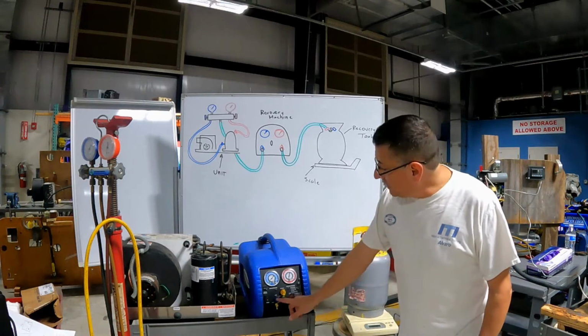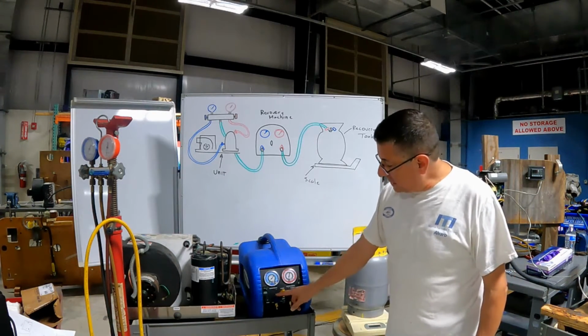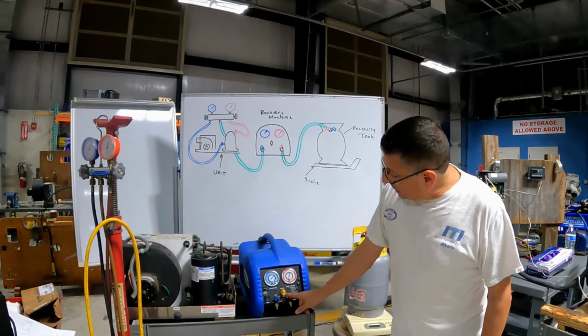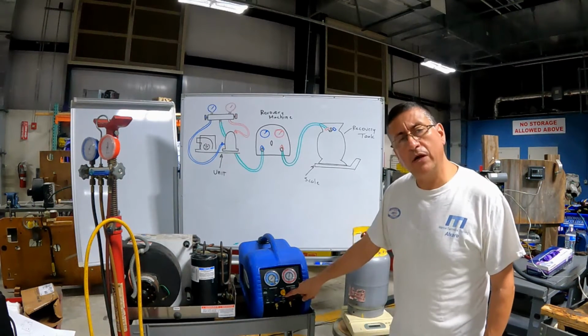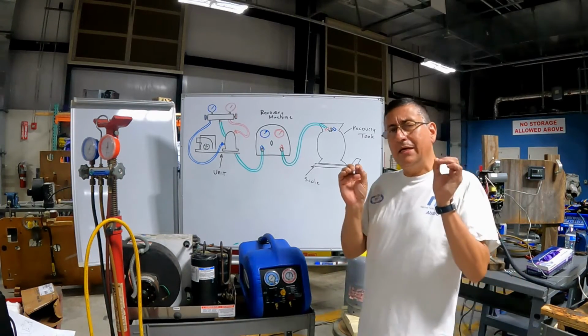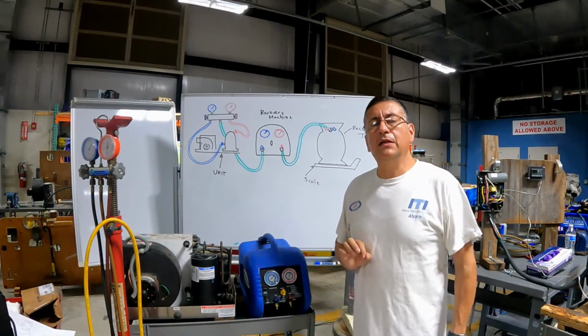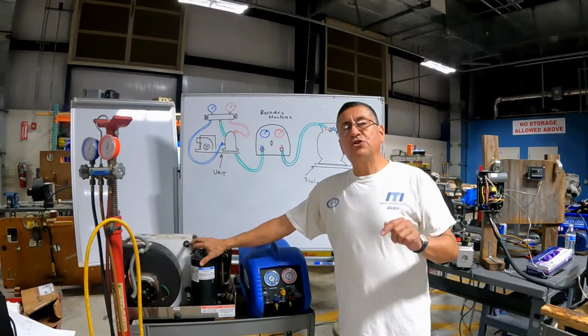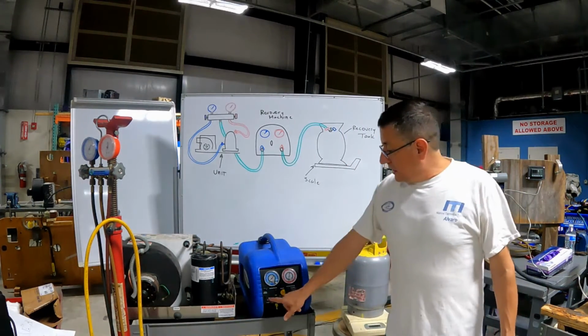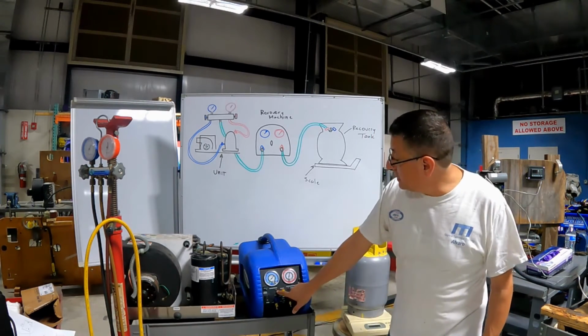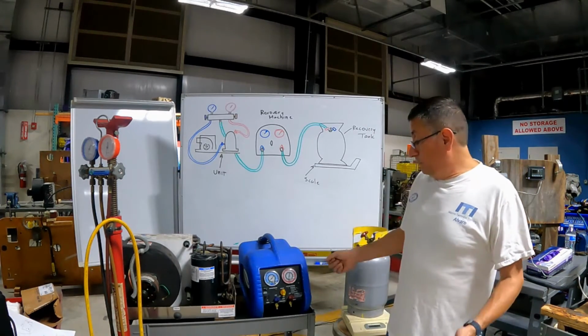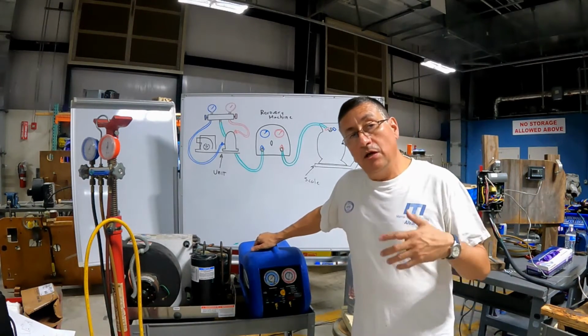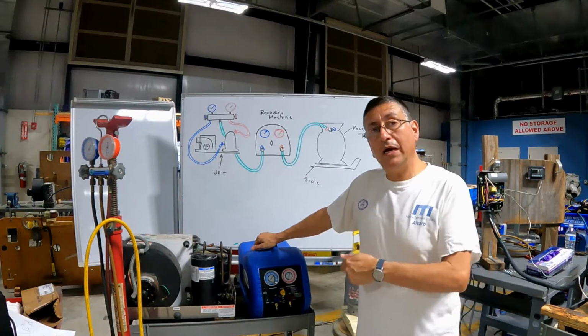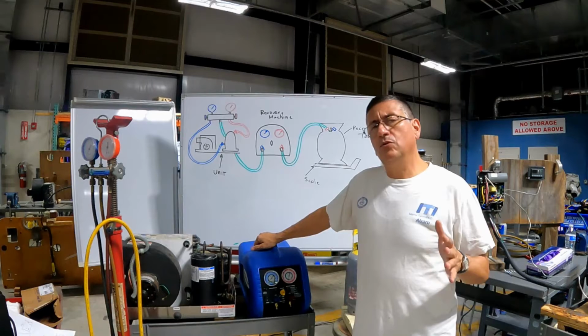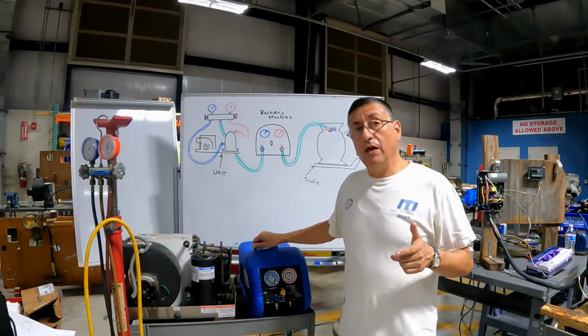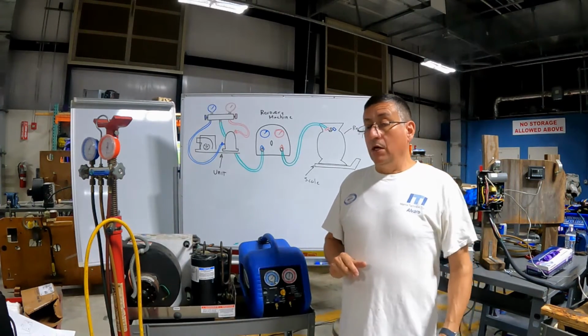Remember that this equipment has two valves, one valve for the low pressure side and the gauge for the low pressure side, another valve for the high pressure side, and the middle one in order to select recover or purge. We are going to purge the system at the end of the process in order to eliminate small amounts of refrigerant inside of the unit. We are going to purge the system at the end of each method. All right, and the on-off switch, and the LED to indicate that the process is complete. It's simple. This is a great piece of equipment. If you will be dedicated to working on air conditioning equipment, I recommend you try to buy one of those units. There are different manufacturers. Try to check the reviews of the equipment on the internet in order to buy the best equipment possible. Ready? We are ready to start.